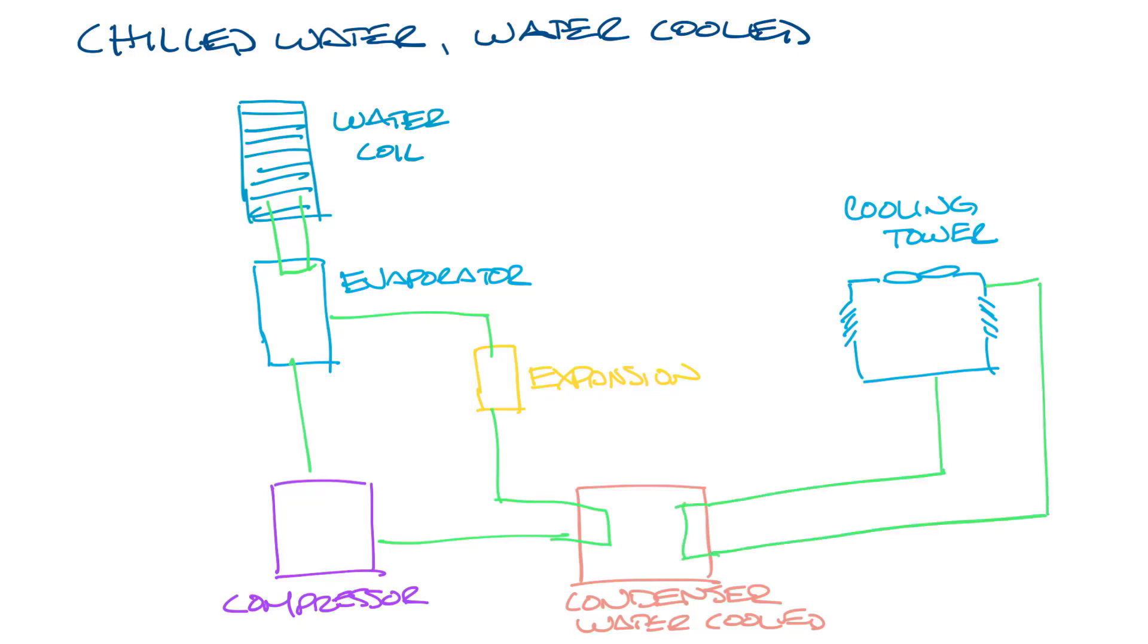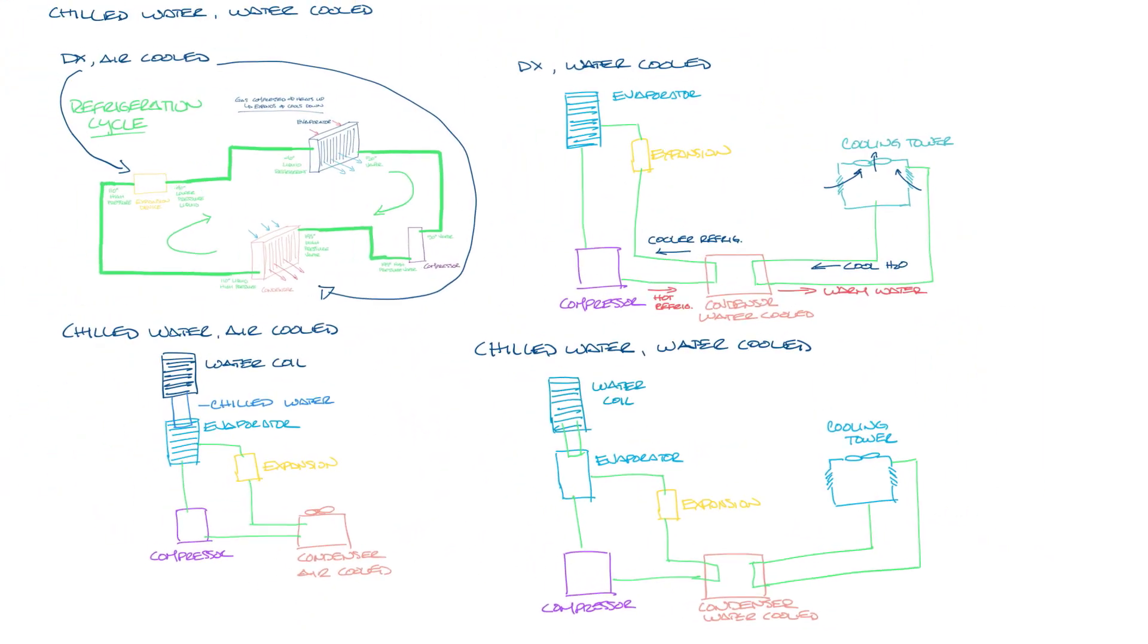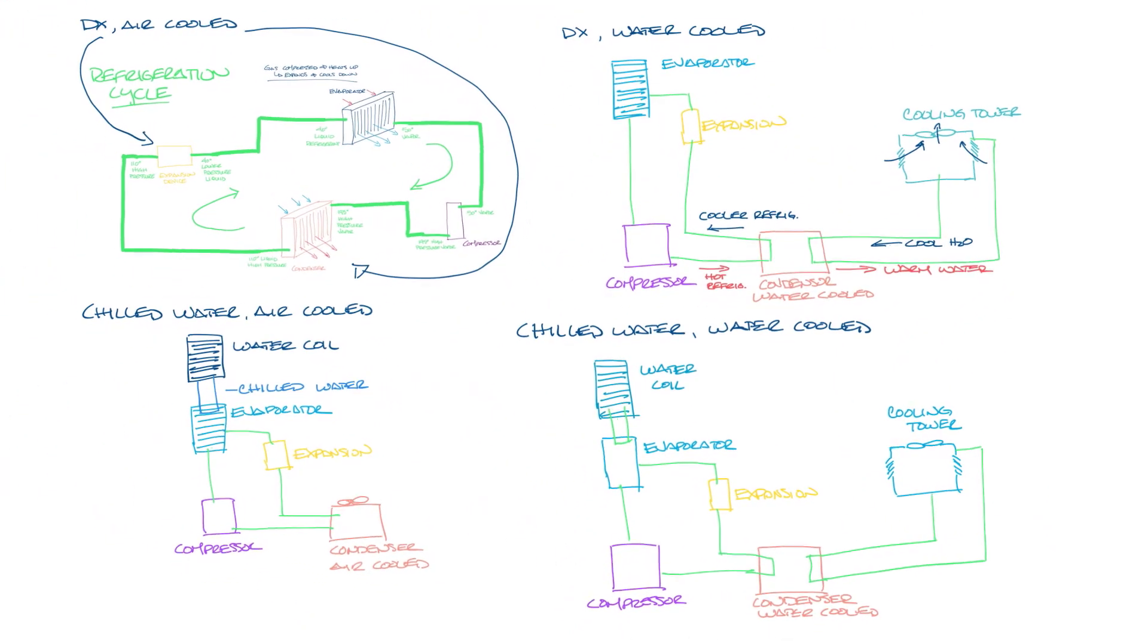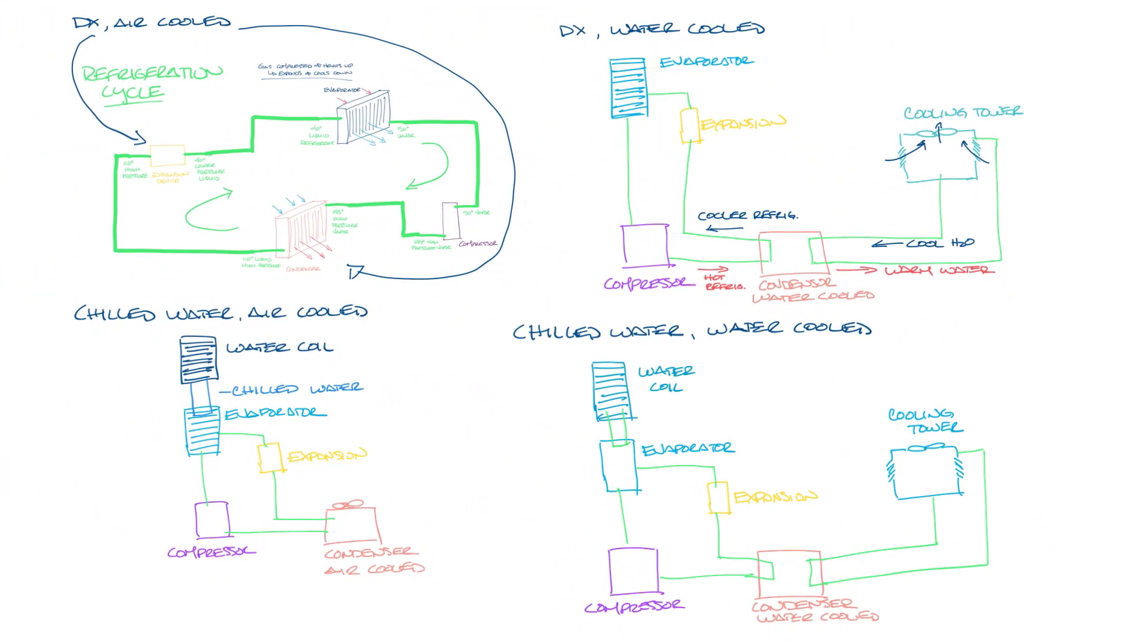Okay, let's bring all of these back on screen so that you can look at all of them at the same time. In a DX central air conditioning plant, the air used for cooling the room is directly chilled by the refrigerant in the cooling coil of the air handler. In a chilled water central plant system, the chilled water is piped to the air handler to supply the cooling, so the refrigerant is cooling the water and then the water is cooling the air.